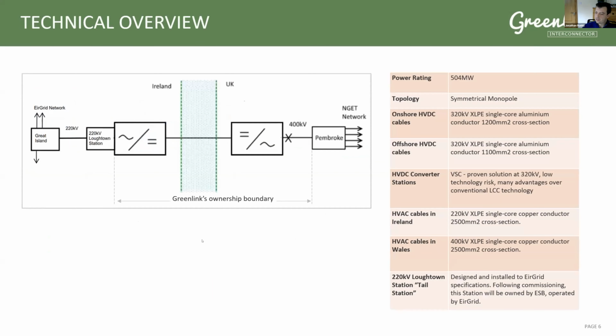So I guess a few more details on that, which might be of interest to this audience. The symmetrical monopole cable itself is a 320 kV XLPE, about 1200 millimeters squared, so it's quite a decent power carrying capability in the two cables. The offshore DC cable is a bit smaller. The converter stations, compared to Moyle, are a VSC, voltage source converter solution, instead of the conventional LCC technology. This is the same technology as EWIC employs as well, with maybe a newer generation of the control and the system involved around that.